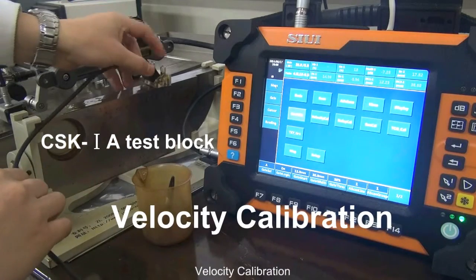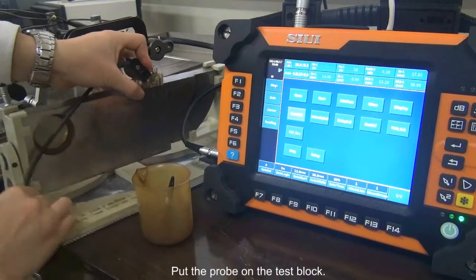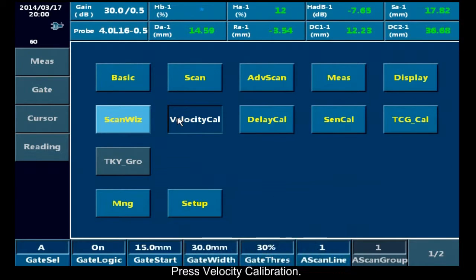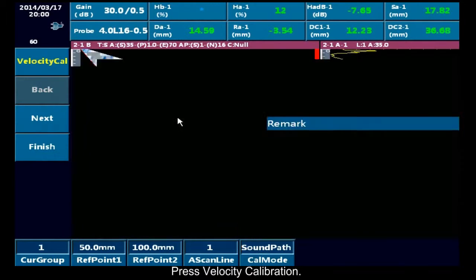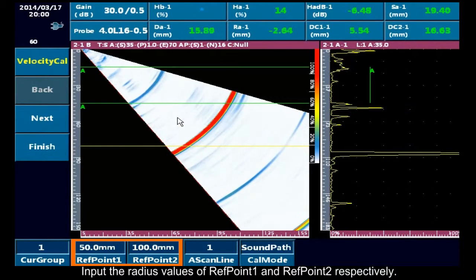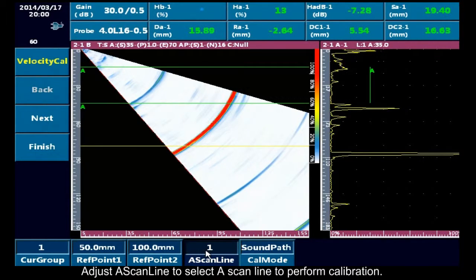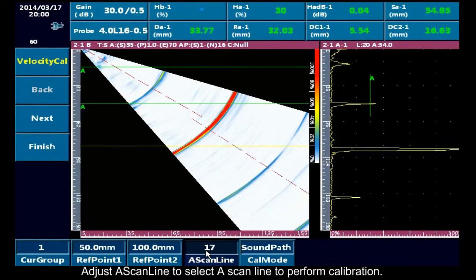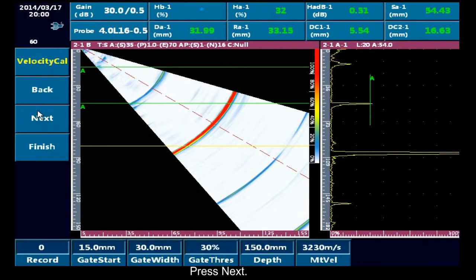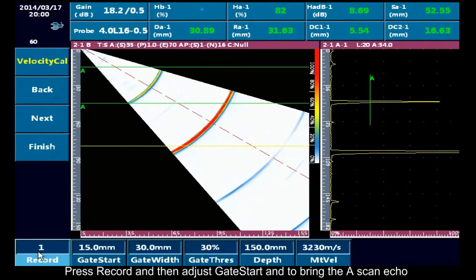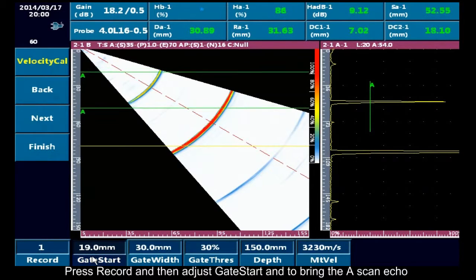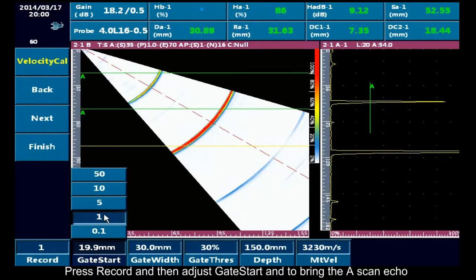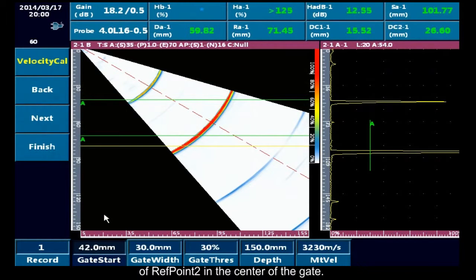Velocity calibration. Put the probe on the test block, and then press velocity calibration. Input the radius value of reference point 1 and reference point 2 respectively. Adjust A scan line to select A scan line to perform calibration. Press Next. Press record and then adjust gate start to bring the A scan echo of reference point 2 in the center of the gate. Press record.